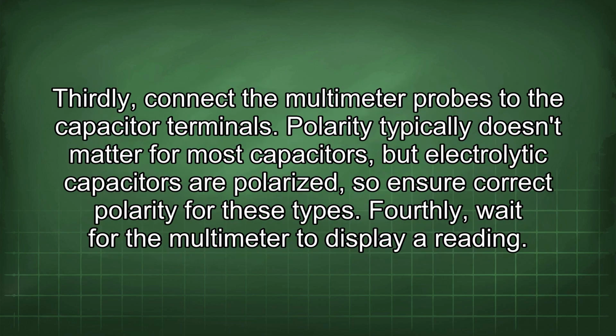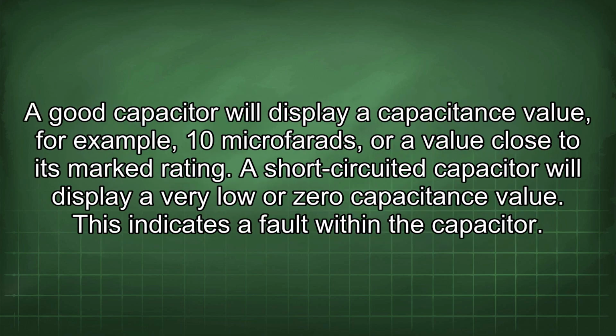Thirdly, connect the multimeter probes to the capacitor terminals. Polarity typically doesn't matter for most capacitors, but electrolytic capacitors are polarized, so ensure correct polarity for these types. Fourthly, wait for the multimeter to display a reading. A good capacitor will display a capacitance value, for example, 10 microfarads, or a value close to its marked rating.